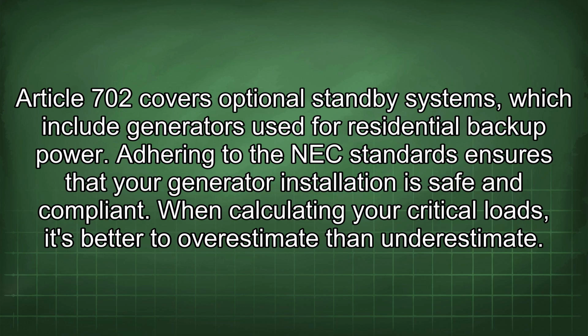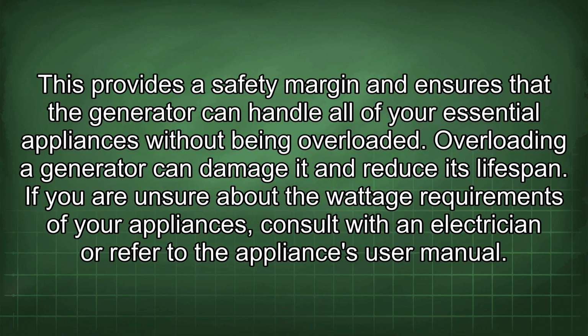When calculating your critical loads, it's better to overestimate than underestimate. This provides a safety margin and ensures that the generator can handle all of your essential appliances without being overloaded. Overloading a generator can damage it and reduce its lifespan. If you are unsure about the wattage requirements of your appliances, consult with an electrician or refer to the appliance's user manual.